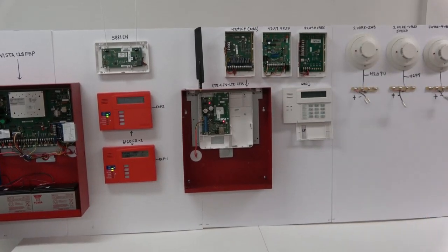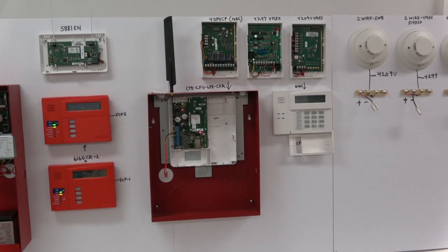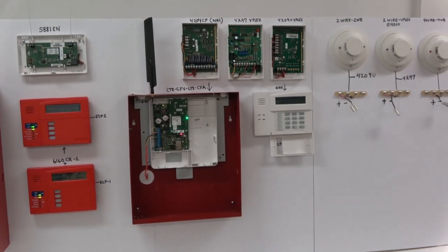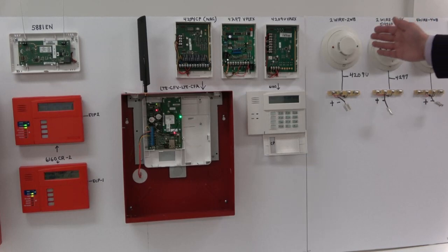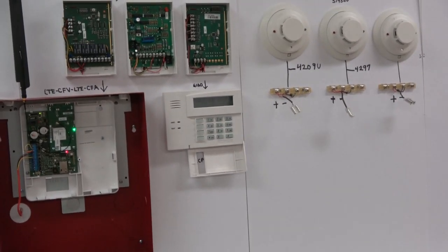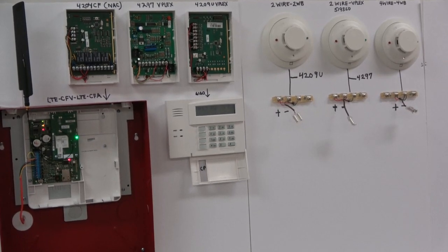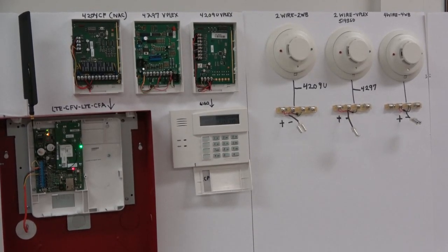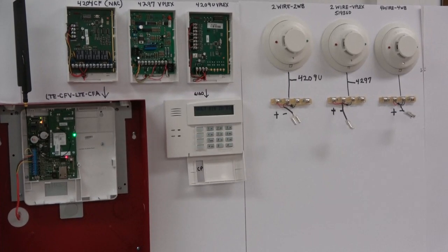This is a 4204CP NAC module that also connects to the ECP-1 bus. This is a 4297 V-Plex module which connects to both the bus for positive and negative and the polling loop. This is a 4209U V-Plex module which also connects to positive and negative for the data bus and the polling loop. This is a 2-wire smoke detector 2WB that connects to the 4209U module. This is a 2-wire V-Plex model number 5193 SD which connects to the 4297 module. 4-wire smoke detectors such as this System Sensor 4WB connect directly to the control unit. Positive and negative power for this smoke detector and all smoke detectors on this 4-wire loop connect directly to the bus.